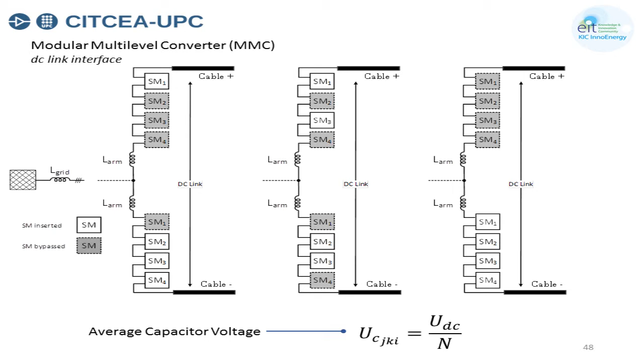If you look at this image, if these 4 are bypassed, all the DC voltage at the DC link is sustained by these 4 capacitors, right? So at each individual submodule, the voltage across it is VDC divided by the number of submodules in each arm. In this case, the voltage at this capacitor is VDC divided by 4.